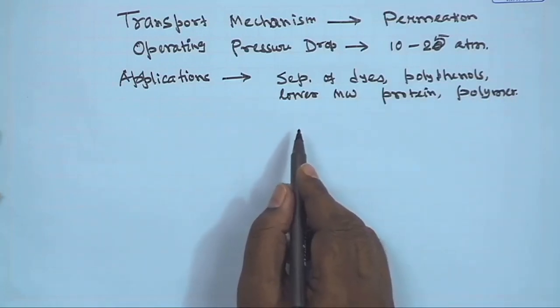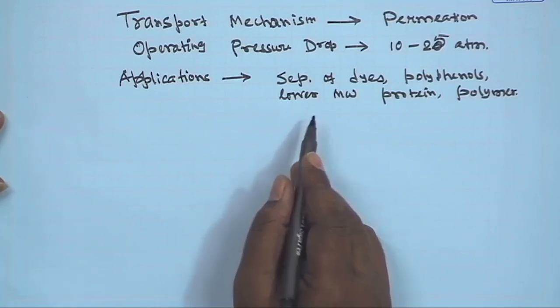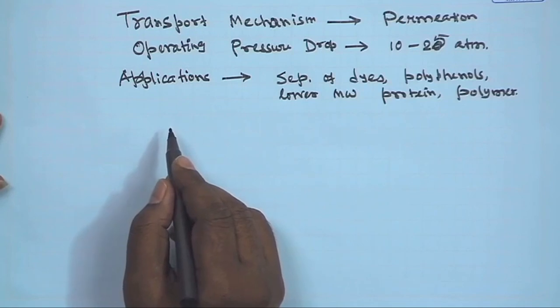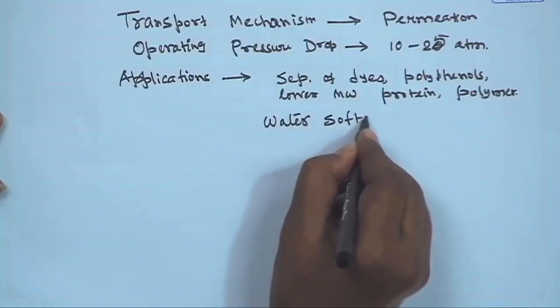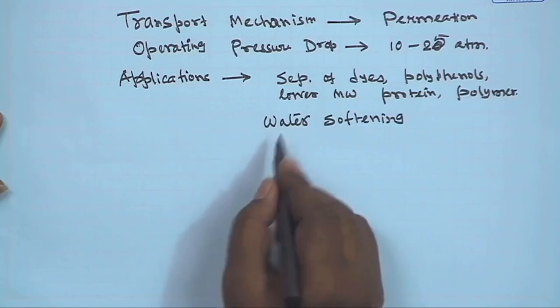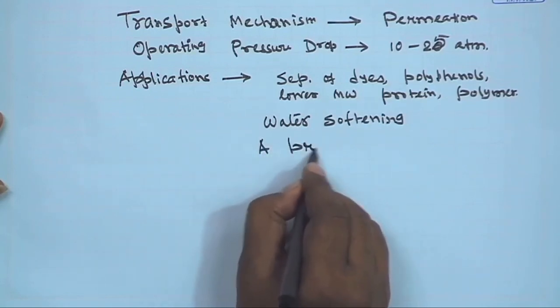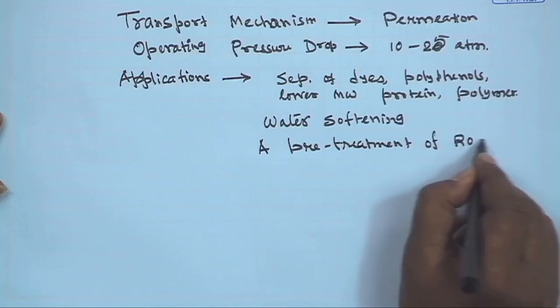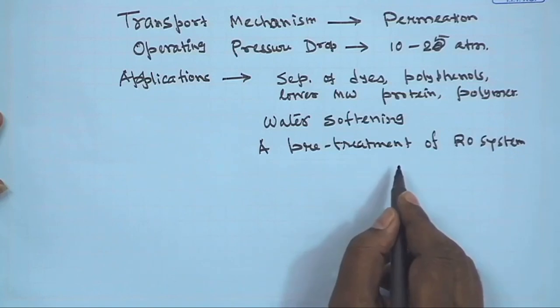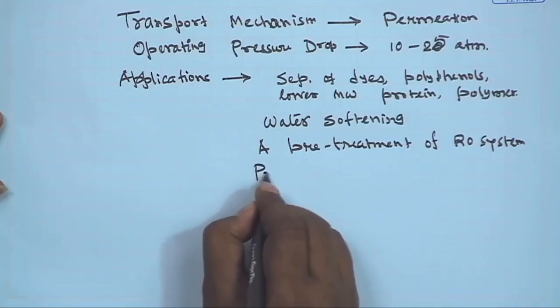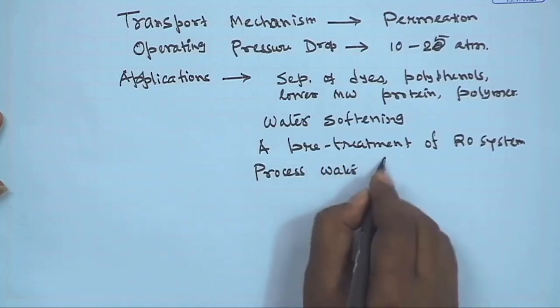Applications of nanofiltration include separation of dyes, polyphenols, lower molecular weight proteins, and polymers. It has wide application in the pharmaceutical industry and can be used for fractionation. It can also be used for water softening, because divalent salts like calcium, magnesium, and iron can be removed by nanofiltration. Nanofiltration is also used as a pretreatment for reverse osmosis systems, so that some salt is removed by nanofiltration and the load on the reverse osmosis system is reduced.